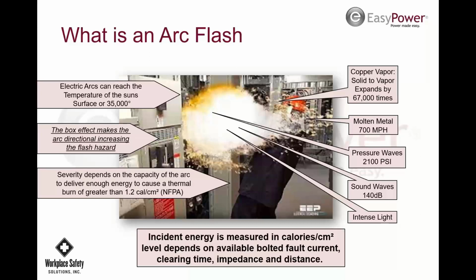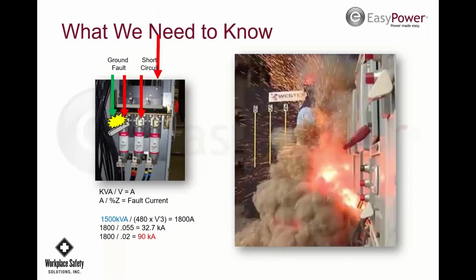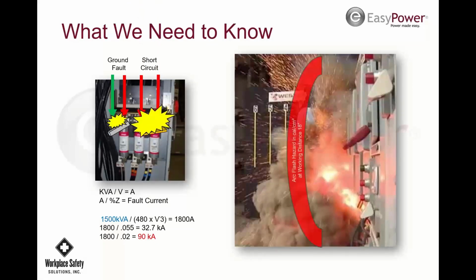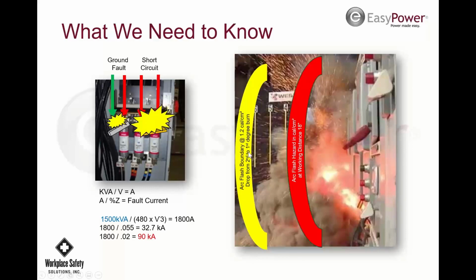So that's something that has to be considered when you're doing a study of that, and that's why you consider the wire types and lengths and all that. But also motor load has a factor on that. So if you've got 50 horsepower motors and larger, that can also cause more inductance, and that's going to cause more overall impedance, and that's going to bring down your fault current and bring up your clearing time as well. So that does have an impact on there. Okay, and it's all part of the study. We did this. So we need to know what our arc flash hazard is at 18 inches, and we need to know what our arc flash boundary is so we can keep non-qualified people safe by barricading at that level. So that's the barricade. That's the 1.2 calories area. Up here, it's going to be much higher, and we just need to make sure we gear up for that level before we open up any cabinets.